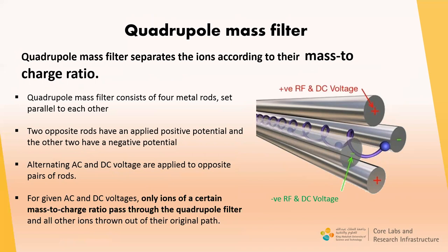The quadrupole mass filter is the heart of the ICP-MS spectrometer. It separates ions according to their mass-to-charge ratio and scans ions in mass sequence from low mass to high mass. The quadrupole mass filter consists of four metal rods set parallel to each other; two opposite rods have an applied positive potential and the other two a negative potential. Alternating and direct voltages are applied to opposite pairs of rods, so that for a given voltage setting, only ions of a certain mass-to-charge ratio pass through the filter while all other ions are thrown out of their original path.